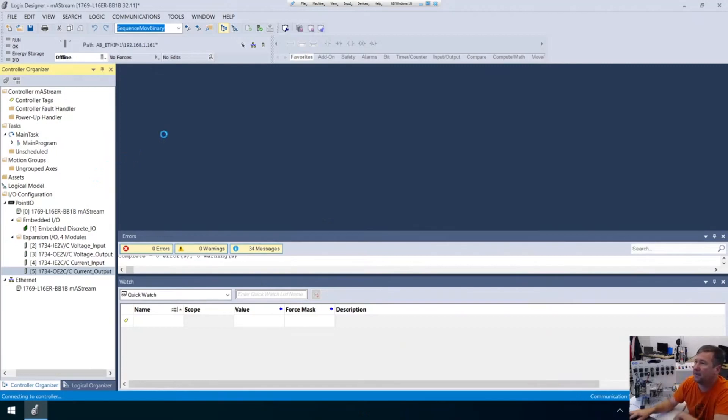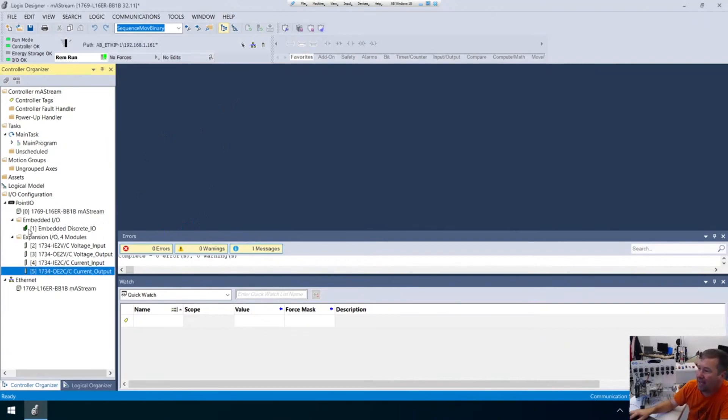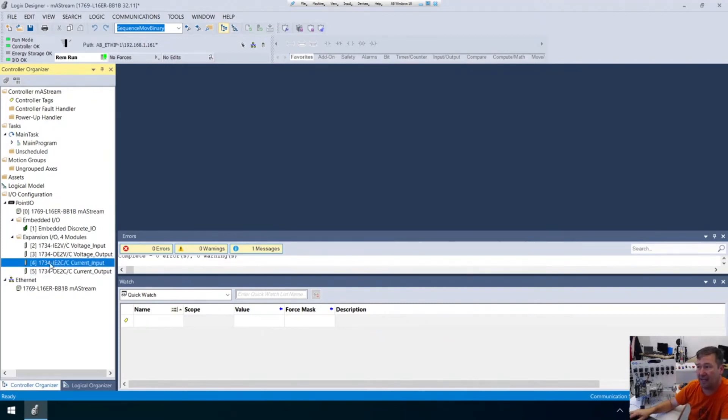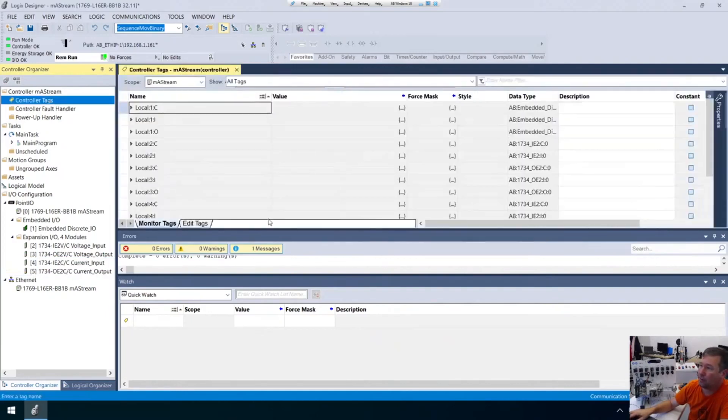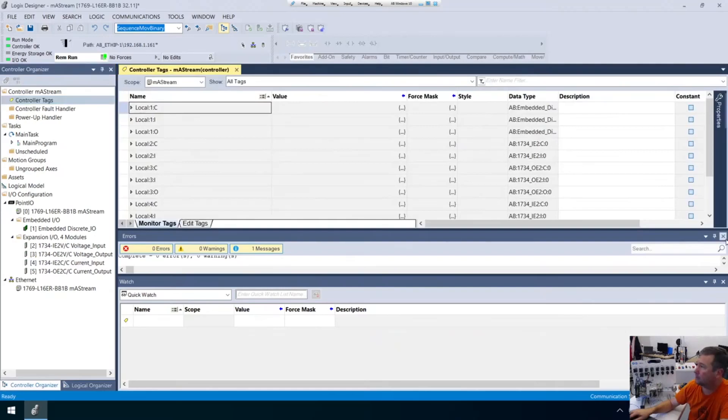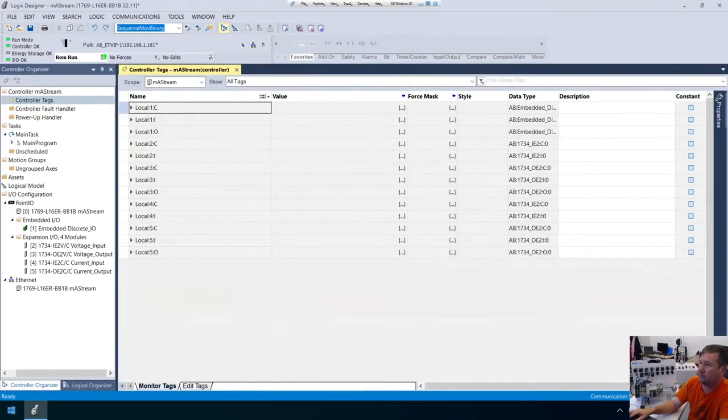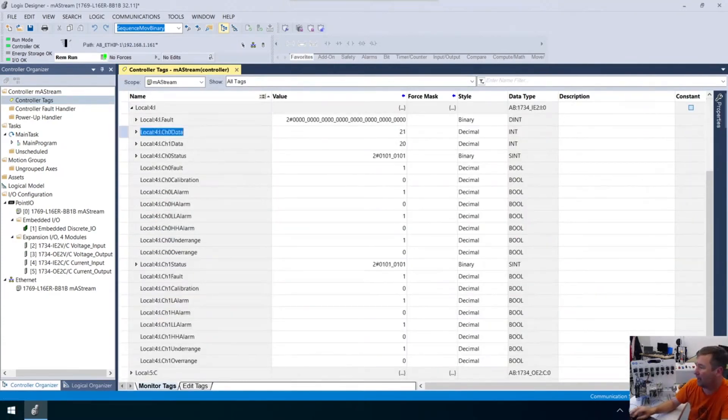Now the next thing we're going to do is figure out where this analog input is. I added them in these expansion modules here, and if you notice there is a number in front of this expansion. Our embedded is one, and that means that's local colon one. Our first module is going to be two, our second module is going to be three, and our third module is going to be four. So we need to go to local four input, and we are looking at this channel data right here.